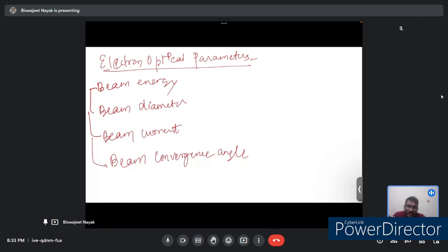One of the fundamental parameters is the energy of the electrons in the beam. This parameter represents the initial energy of the electrons as they enter the SEM chamber. Beam energy has a direct effect on many important aspects of SEM operation, such as the size of the excitation volume and the intensity of X-rays emitted.